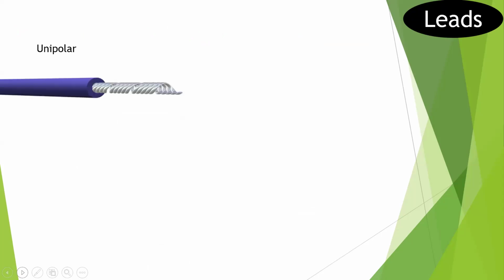So the leads, normally there are two types of leads. Actually, there are many types of lead, but I'm concentrating on the simple type of pacemaker. The unipolar lead is a very small lead with one central ball which is connected to the myocardium. And as I said, the cathode, which is basically the ball through which depolarization happens to the myocardium, is at the tip of the lead, while the anode, through which the stimulation goes back, is the tissue of the human being himself. So the can represents the anode for the device.